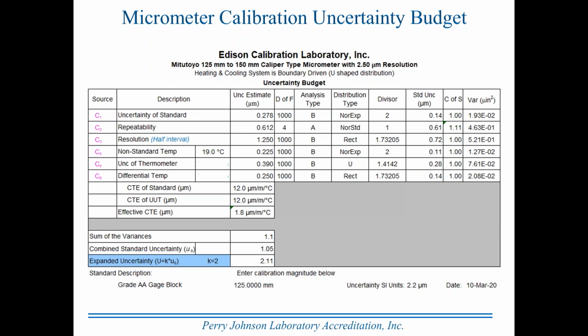It might be a CMC budget where you're putting in theoretical values of the best equipment under the ideal conditions. So instead of having 19 degrees C for the calibrating temperature, it would be 20, because that's ideal. But you would take the values you have for uncertainty, put them in this column, along with degrees of freedom, type of analysis, normal or expanded, and what the divisor is, and once you put this in, it does the calculations across here.